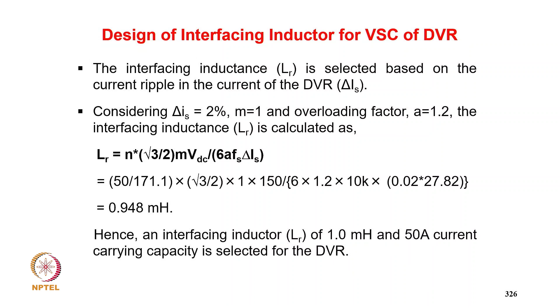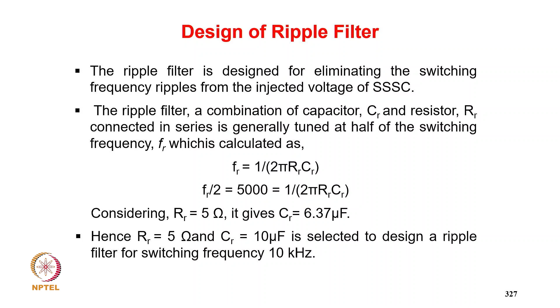The ripple filter is designed for eliminating the switching frequency ripple from the injected voltage of the VSC. The ripple filter, a combination of capacitor CR and resistor RR connected in series, is generally tuned at half the switching frequency, which calculates as FR equal to half, 1 upon 2 pi RR CR, so FR by 2 equals 5000 equals 1 upon 2 pi RR CR. Considering RR equal to 5 ohm, CR gives 6.37 microfarad. Hence RR equal to 5 ohm and CR equal to 10 microfarad is selected to design the ripple filter for the switching frequency of 10 kHz.